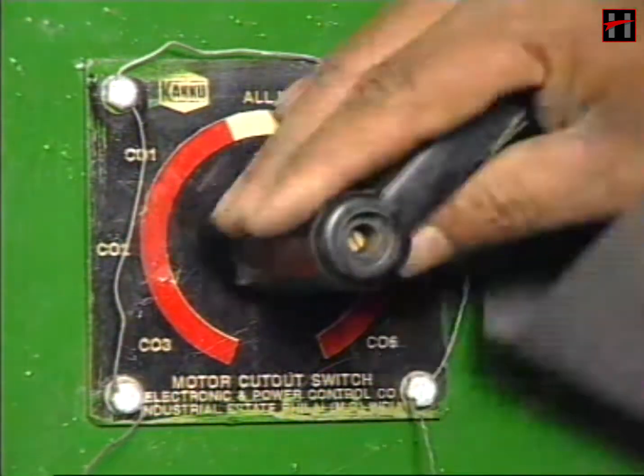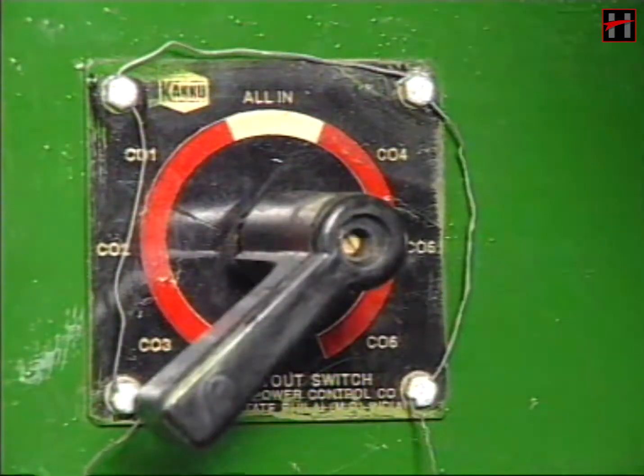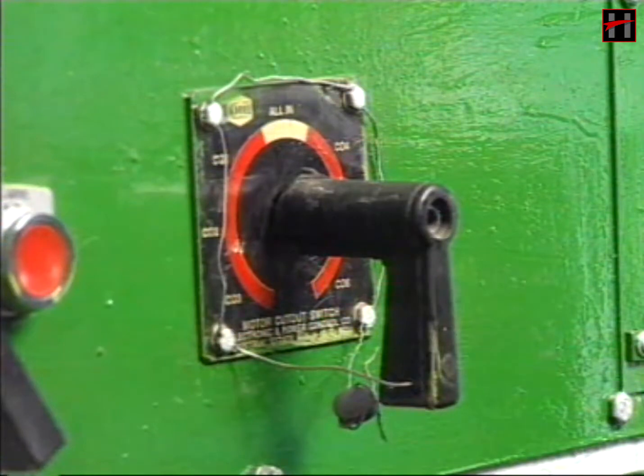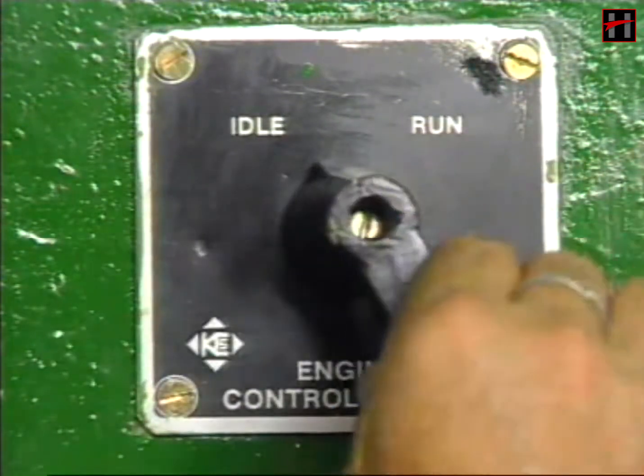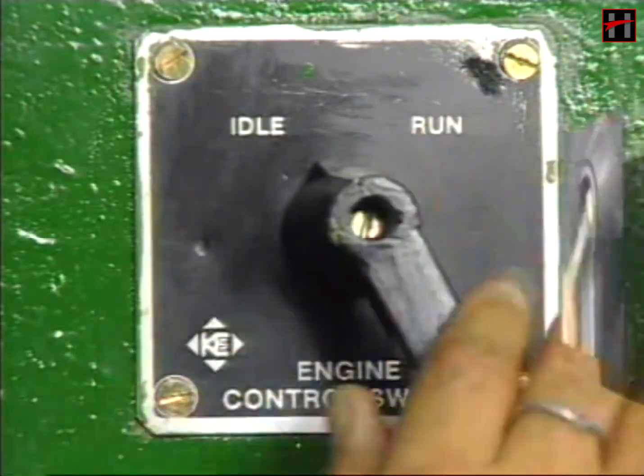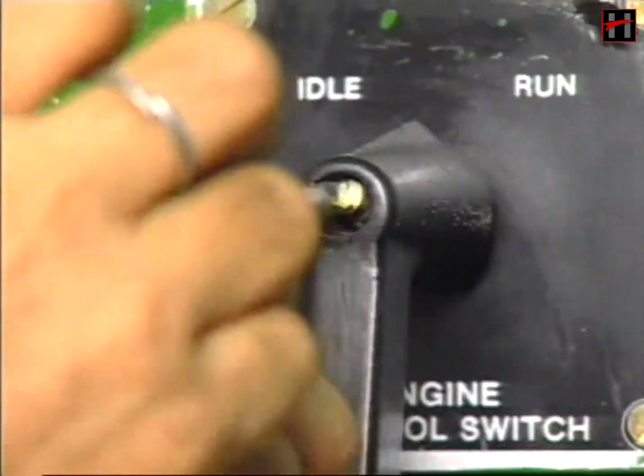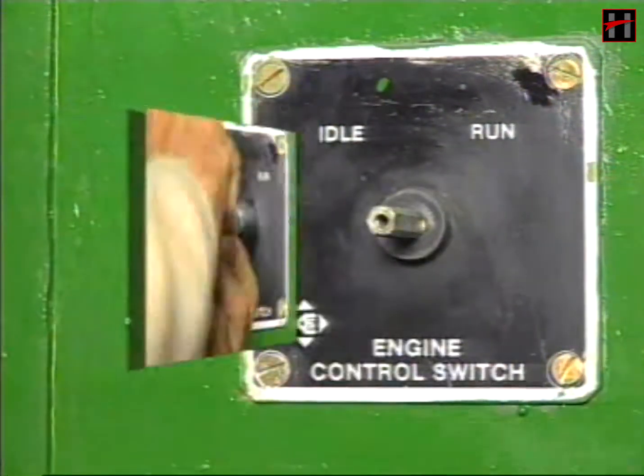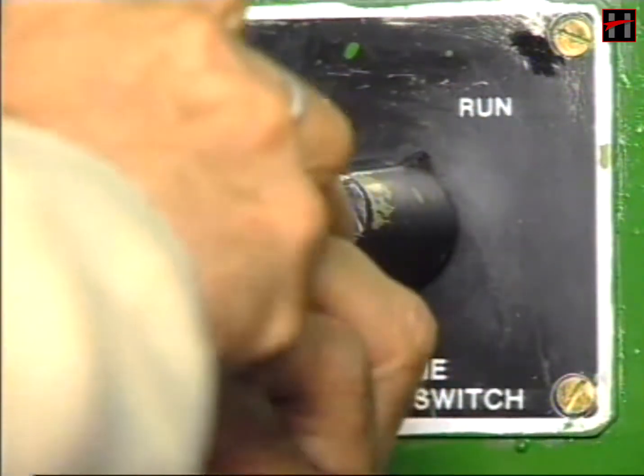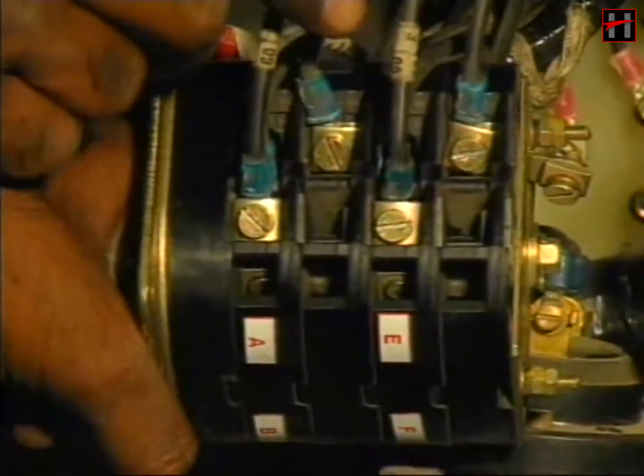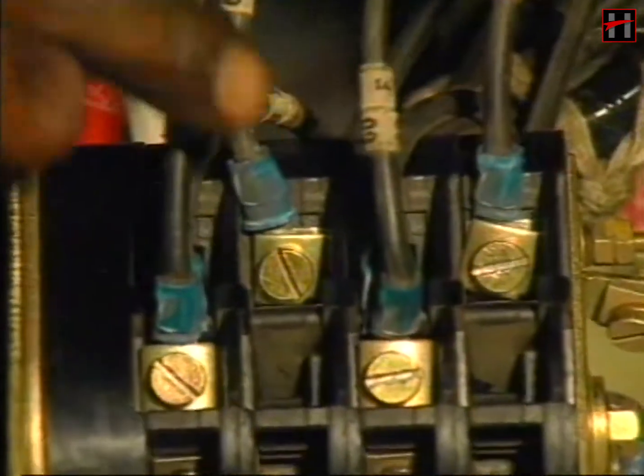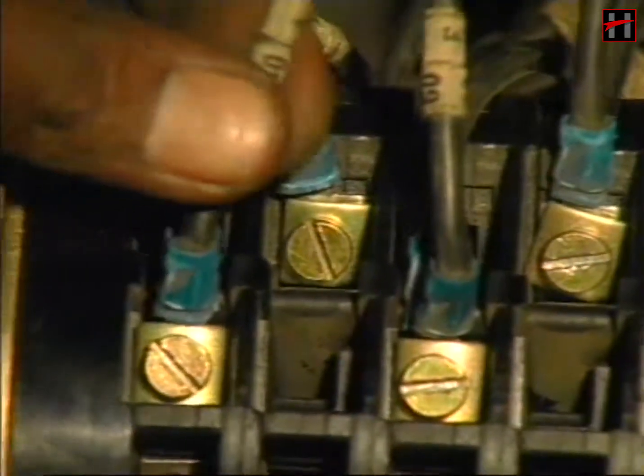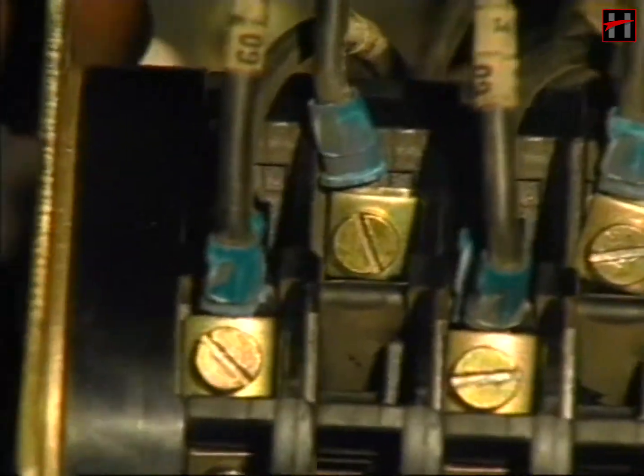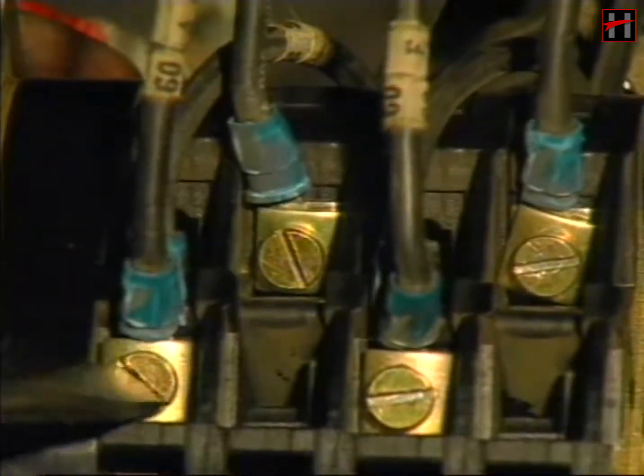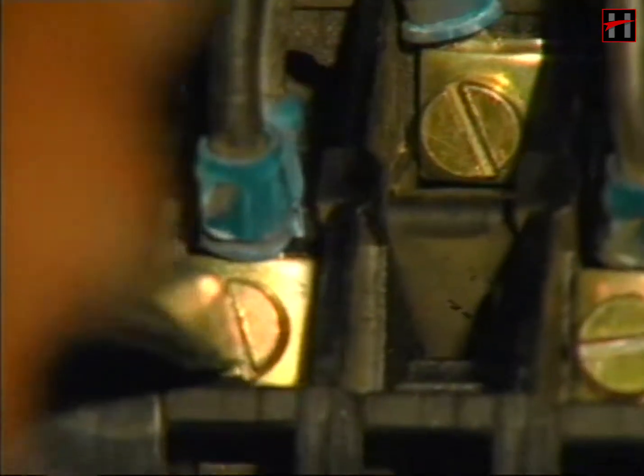Remember, after checking the operation of the motor cutout switch, secure the sealing of the motor cutout switch. The knob of the switches should not have any excessive play. If there is excessive play between the knob and the shaft, change the switch. Take out the switches from their sockets and check their terminal connections. If any terminal connection is found loose, tighten it, and if any terminal connection has broken, rejoin the wire to the connection.